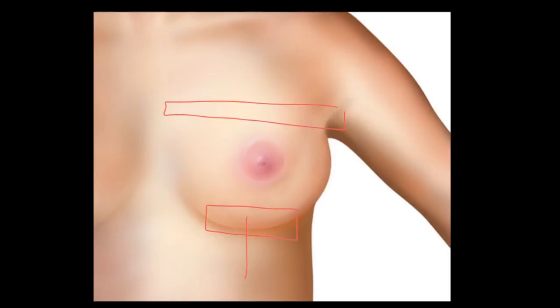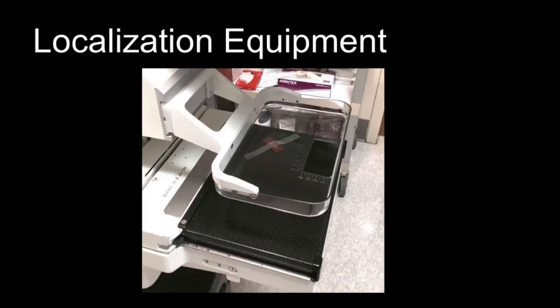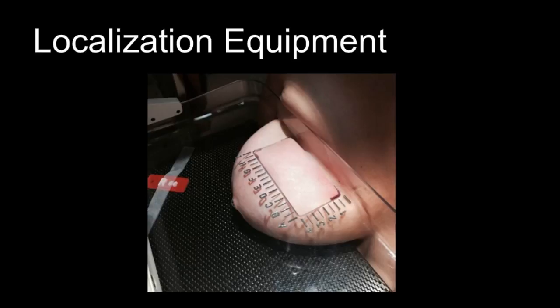This concept is better understood with visualization of the localization equipment. The breast is placed in the CC position with the open grid on the side of needle entry and the receptor plate on the under surface of the breast. The technologist aims to position the target within the center of the grid. Marks are placed in the corner of the open grid to monitor for movement. The alphanumeric grid along the open grid surface is used for target localization, with opaque numbers and letters serving as reference for determining the needle entry point.